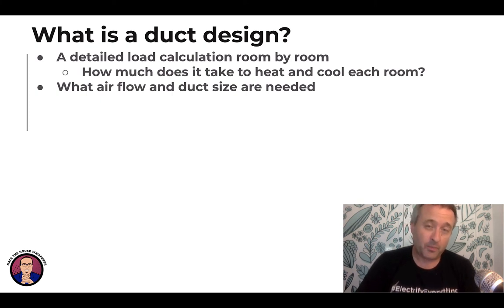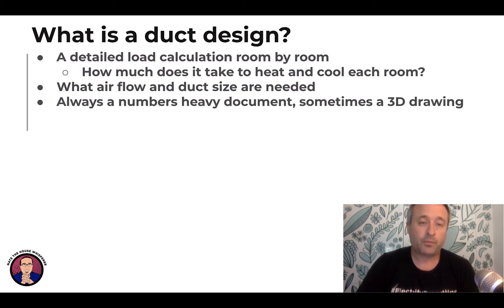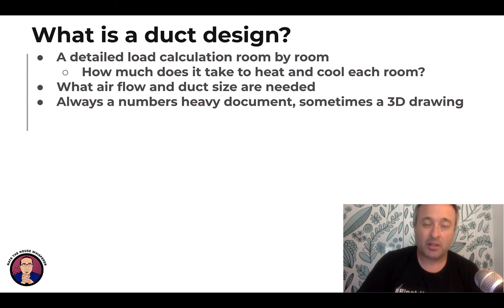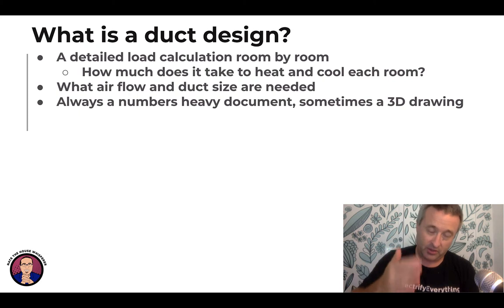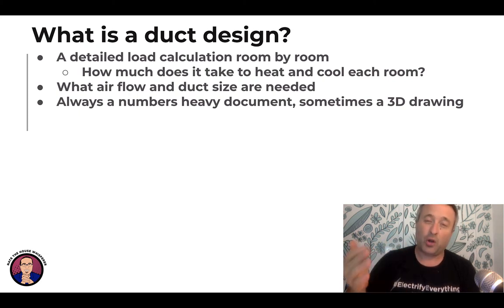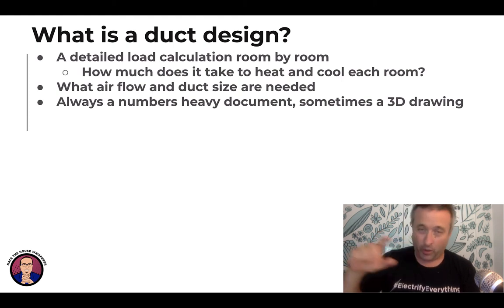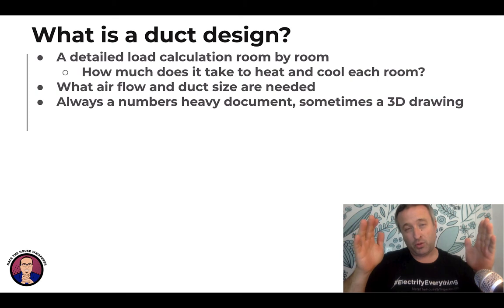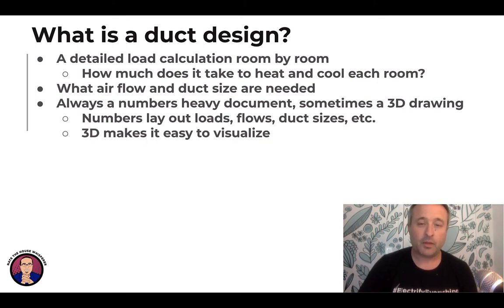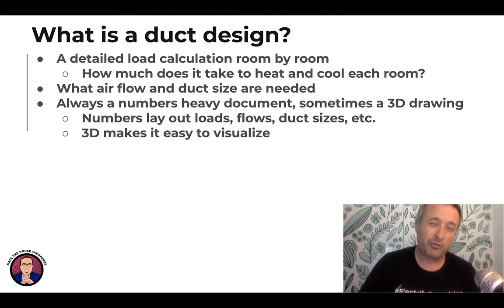The calculation also helps with what airflow is needed. If you know how many cubic feet per minute you want for heating and cooling to a room, that helps you figure out what size duct you need to run, and what size duct goes back to what size trunk. The trunk is related to what size equipment you buy — because the rule of thumb is 400 CFM per ton (per 12,000 BTUs). You can go as low as 275 and almost freeze the coil. Out West, friends will run 600–700 CFM per ton because they don't want dehumidification in the summertime. So 400 is kind of the middle-of-the-road assumption. There are two main documents you'll see in a duct design: one is numbers-heavy, and the other is a 3D drawing — which helps you visualize where to run the duct, what size, and what to do with headspace and joist clearance.